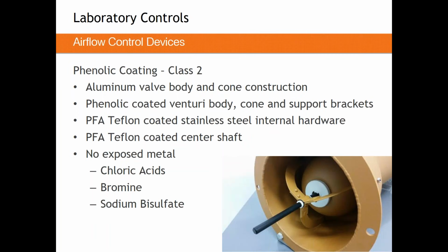The next nearly 5%, however, are this class 2 coating. In a class 2 coating, we find that a phenolic coating covers an even broader spectrum actually than stainless steel does. So in this style of coating, we're going to coat every metallic part with either Teflon or phenolic. In this style of valve, the Teflon goes from PTFE to PFA, which is slightly more costly, but it covers a bigger, better spectrum of chemicals that it's resistant to. So if you're dealing with the chloric acids, bromine, there's a couple examples up there, that's when the class 2 device is going to be required.